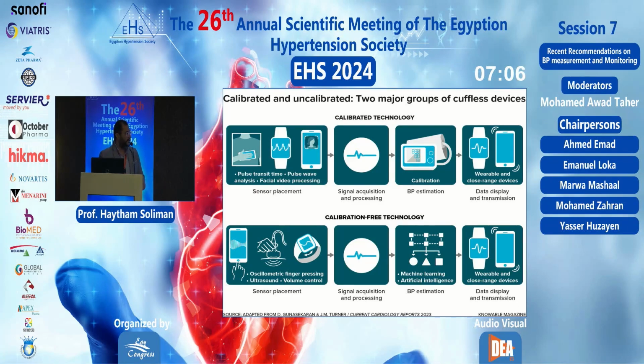So the two types of cuffless devices are the calibrated technology and the calibration-free technology. We think that calibration means comparing the device with the conventional blood pressure device. No, the calibration or non-calibration is inside the process itself. Calibrated devices acquire the pulse or the vibration, get the signal, compare it with a reference inside the device itself, and then give us a reading. The non-calibrated, or calibration-free, technology acquires the information, which is oscillometric or ultrasound, and then gives it to a machine learning process that gives us a reading or information.